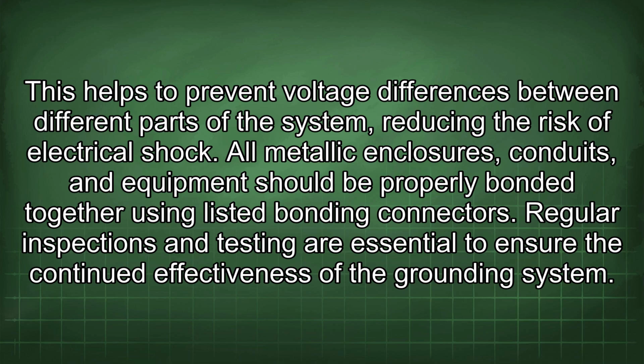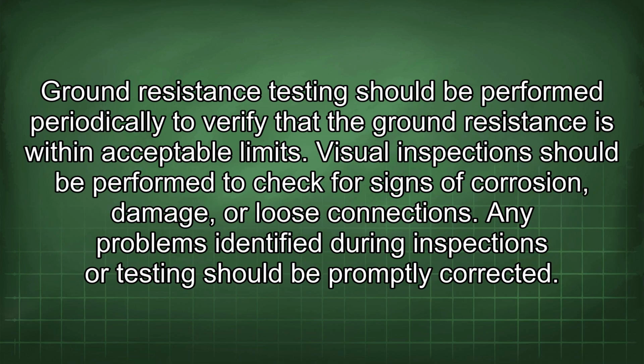Regular inspections and testing are essential to ensure the continued effectiveness of the grounding system. Ground resistance testing should be performed periodically to verify that the ground resistance is within acceptable limits.